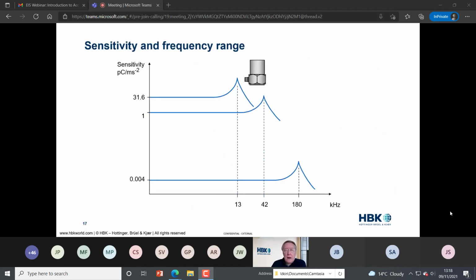Now, as is often the case with lots of different sorts of transducers, generally speaking, a large transducer means that you will have high sensitivity but a relatively restricted frequency range. Whereas at the other end, with a very small accelerometer, you will have a wide frequency range but low sensitivity. And you can see that with an accelerometer, you have a broadly flat part of the frequency response, and then you have really quite a sharp resonance at the end. And it's that resonance that determines the usable frequency range of a piezoelectric device.